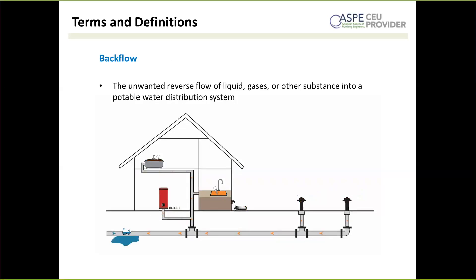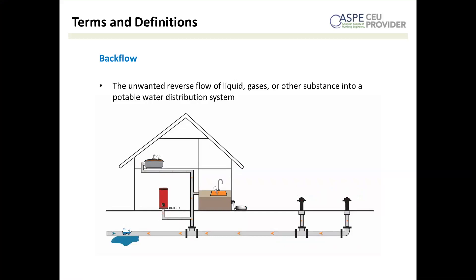Backflow is the unwanted reverse flow of a liquid, gas, or other substance into a potable water distribution system. Our potable water distribution system is built to operate primarily in one direction — from the source to the point of use out of your taps. When that direction reverses and you have cross-connections downstream, you risk introducing contaminants. In the case of a water main break, there's potential to siphon dirty water from bathtubs, glycol from boiler systems, or fertilizer from irrigation systems into the water meant for drinking.